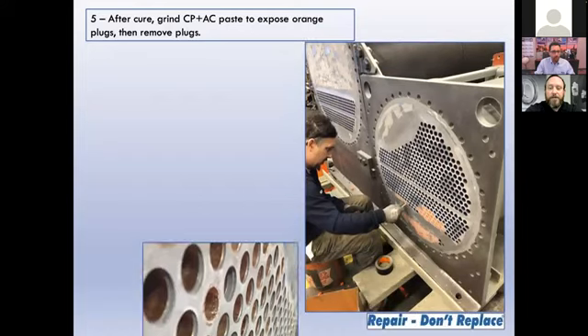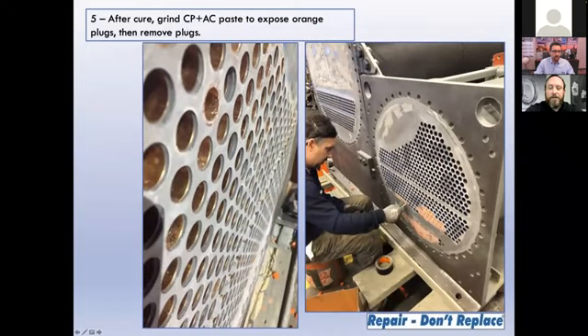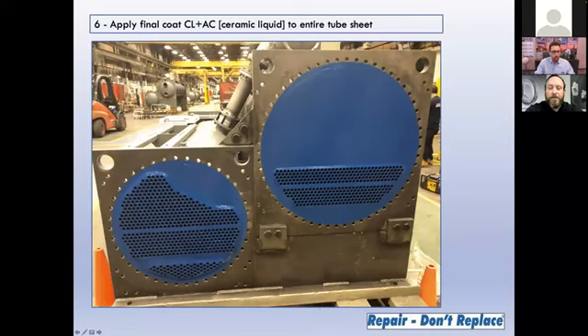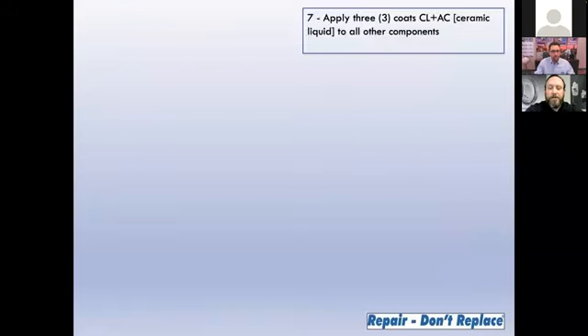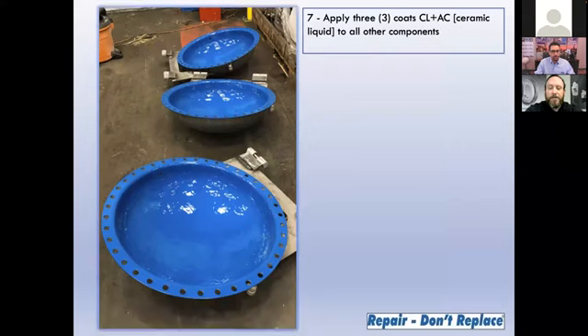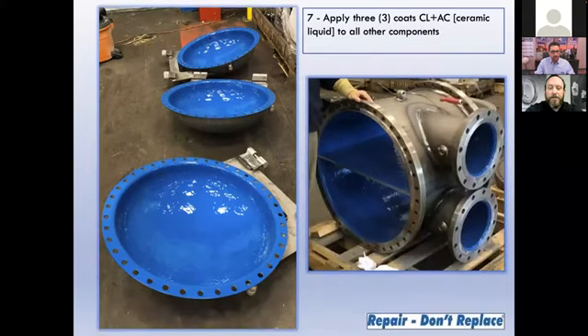Once all of the plugs are removed, this is the type of finish that we're looking for. Smooth, monolithic finish, and no gaps between the CP Plus AC and the copper tubes. This would be the final thing we do for the chillers. We would apply one final coat of Ceramaloy CL Plus AC to the tube sheets, and we apply 3 coats of the Ceramaloy CL Plus AC to the dish return heads and water boxes.